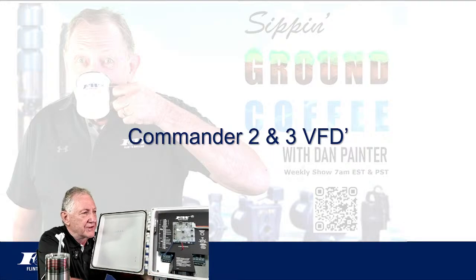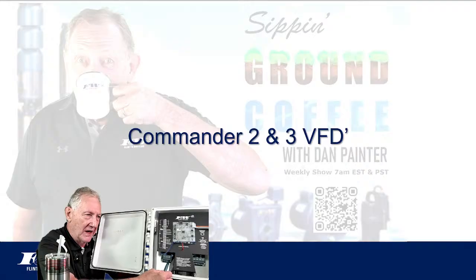All right, so wiring this drive, I mentioned there are openings down here at the bottom to bring your power in, but there's a terminal block over here, and that's where your power is going to come into this drive. It's got an L1, an L2, and a ground. So very well marked, easy to access terminal block to bring the power into the drive.